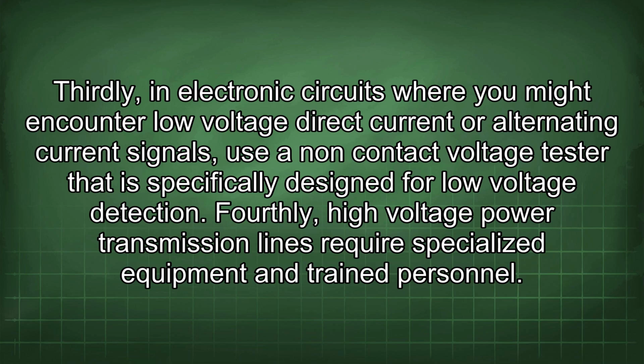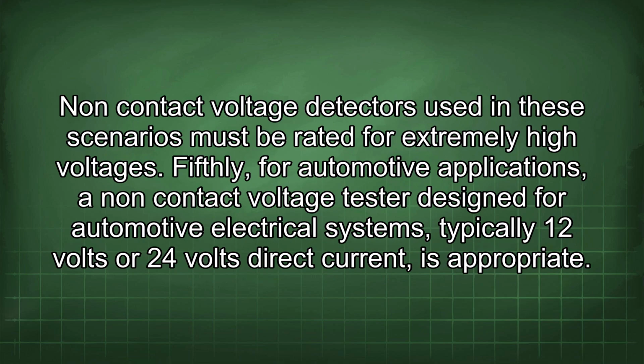Thirdly, in electronic circuits where you might encounter low voltage direct current or alternating current signals, use a non-contact voltage tester that is specifically designed for low voltage detection. Fourthly, high voltage power transmission lines require specialized equipment and trained personnel. Non-contact voltage detectors used in these scenarios must be rated for extremely high voltages. Fifthly, for automotive applications, a non-contact voltage tester designed for automotive electrical systems, typically 12 volts or 24 volts direct current, is appropriate.